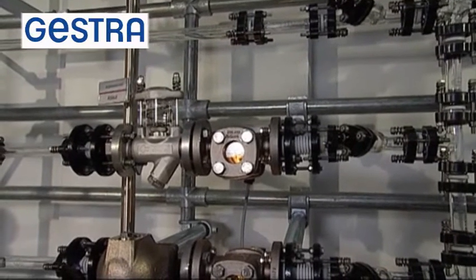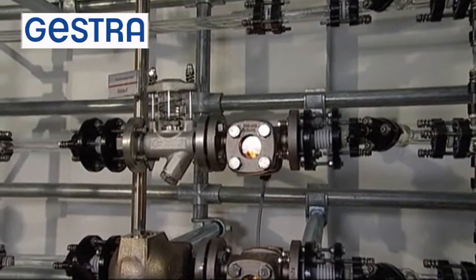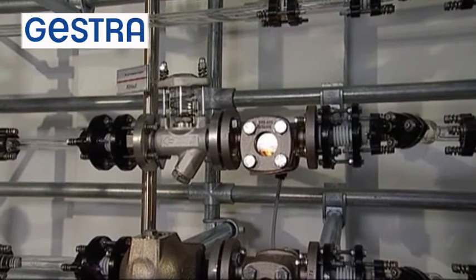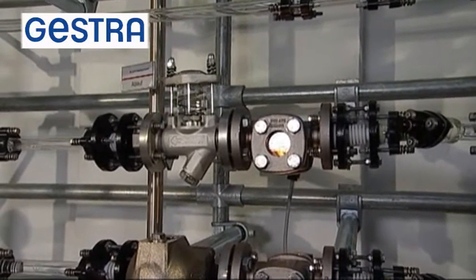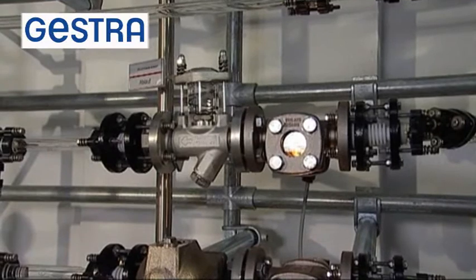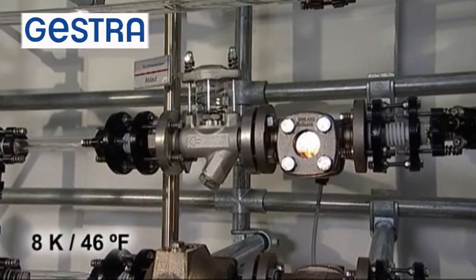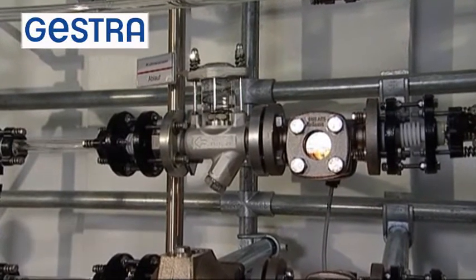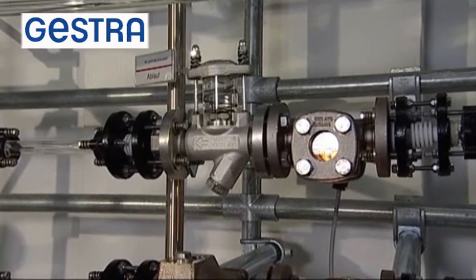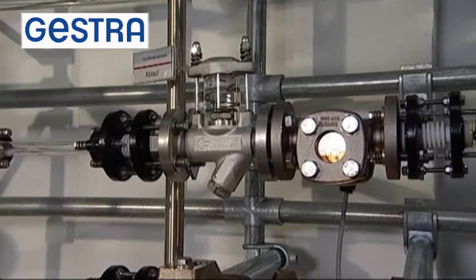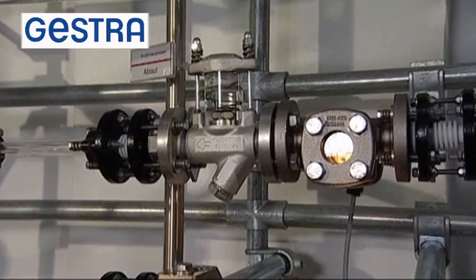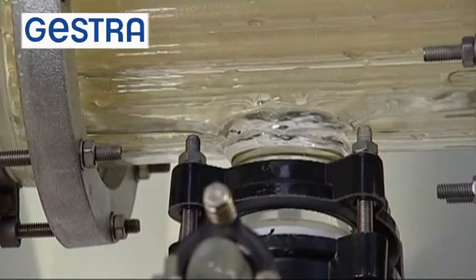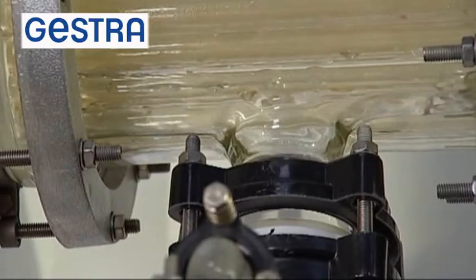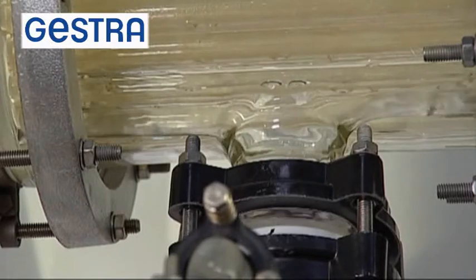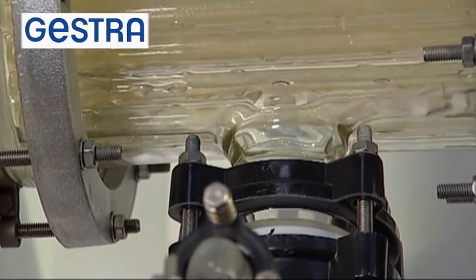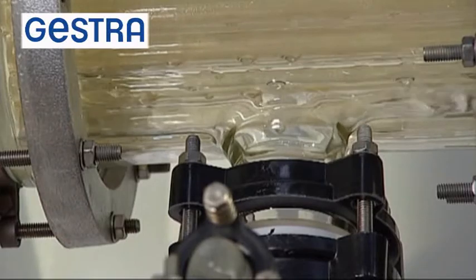The condensate flows through the vaporscope and enters the body of the membrane steam trap. Here we have a steam trap with a single seat membrane regulator and undercooling of 8 Kelvin. As soon as this temperature difference is reached, the steam trap opens and discharges the condensate. When the temperature rises, the steam trap closes again. There is now a slight banking up of condensate until there is again undercooling in the cover and the opening process begins once more.